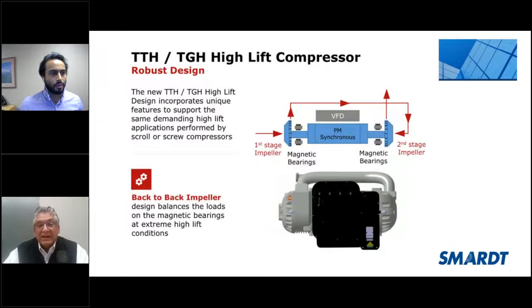I can tell you from my past working with several other vendors, some will say you had a hard time keeping a job, right? But I've worked with Carrier, Trane and York. One of the things that we used to target, as a competitor, quite frankly, was the inability of a Danfoss compressor to have high lift. Well, Smardt has taken care of that problem by introducing a high lift machine, which is really two impellers, a first stage and second stage impeller. That allows the machine to handle both a low leaving water temperature on the cooler side and a higher condenser water entering temperature on the condenser side.